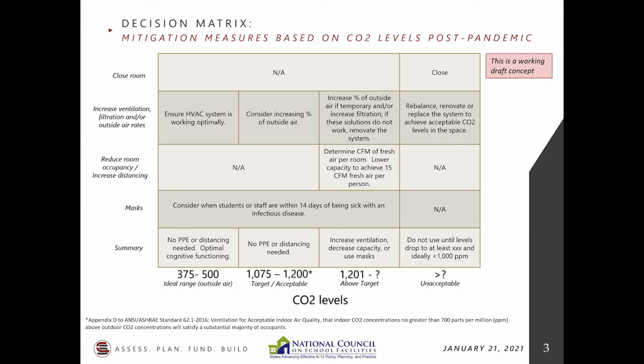And we've done a lot of studies related to what are, quote unquote, naturally ventilated classrooms. The problem with that is naturally ventilated classrooms can mean a lot of different things. Unless you have good cross flow in the classroom, you may not be getting anything coming in and out of that window. Some of the worst schools I've looked at, in terms of ventilation, were in the Netherlands and in Scandinavia, in Finland, where they relied on windows to be bringing in outdoor air. I just want to say that reliance on that alone, you're kind of shooting in the dark. You may be doing better, you may be improving, but you may not be helping a great deal.